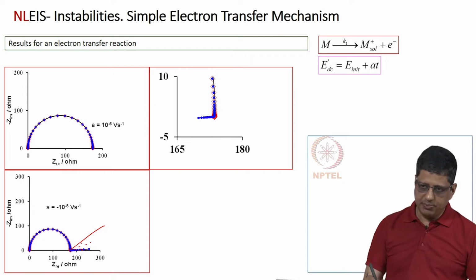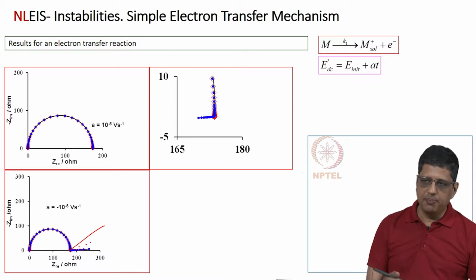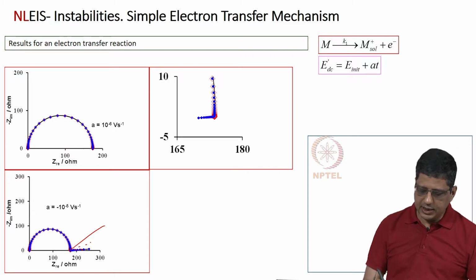At the end of this measurement, if you restart and continue this measurement, take the spectrum again and compare with the first spectrum, do they match? That is one way to check for repeatability, that is one way to check for any changes in the system, is it stable or not stable.